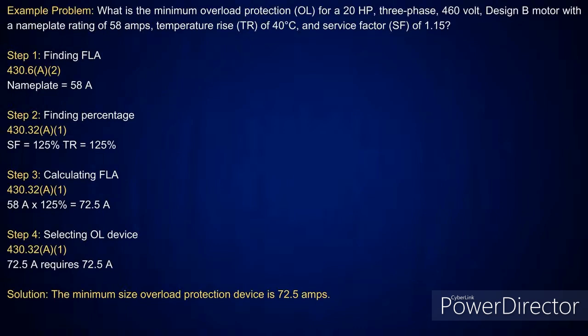All right. So we're going to ask you what the minimum overload protection is for a 20 horsepower, 3-phase, 460 volt Design B motor, and it has a nameplate rating of 58 amps. We're going to tell you it has a temperature rise of 40 degrees C and a service factor of 1.15. Now, when you look at 430.32(A)(1), that's where you're going to pick up your minimum.